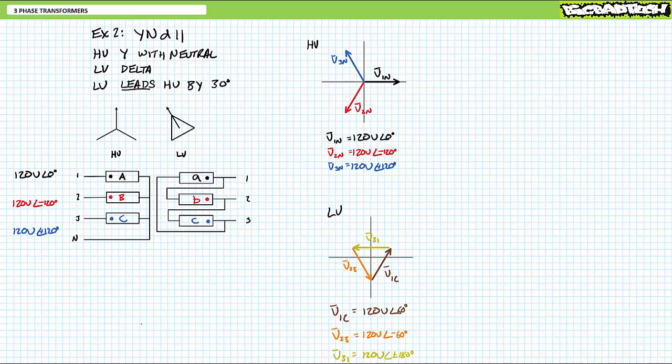When you assemble these phasors end to end as you would a delta, it looks like the low voltage secondary output voltage reference to virtual neutral is tilted 30 degrees in advance, i.e. at 11 o'clock of the primary high voltage inputs, as you'd expect for a YND11 configuration.